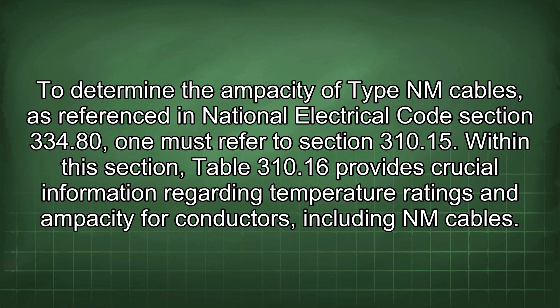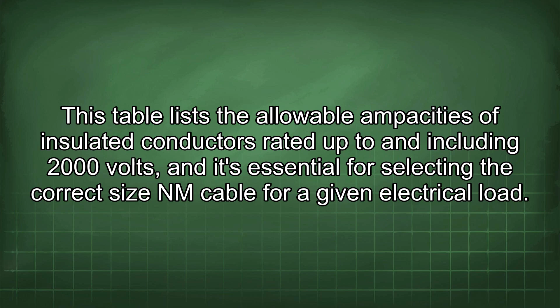To determine the ampacity of type NM cables, as referenced in National Electrical Code Section 334.80, one must refer to Section 310.15. Within this section, Table 310.16 provides crucial information regarding temperature ratings and ampacity for conductors, including NM cables. This table lists the allowable ampacities of insulated conductors rated up to and including 2000 volts, and it's essential for selecting the correct size NM cable for a given electrical load.